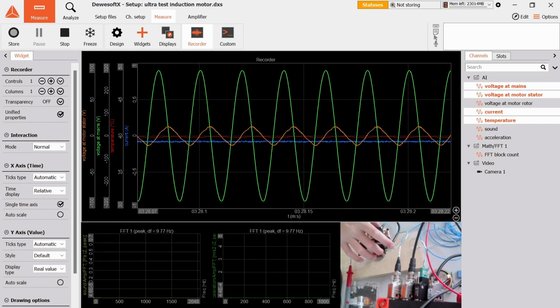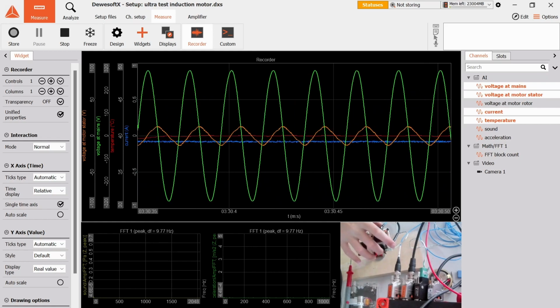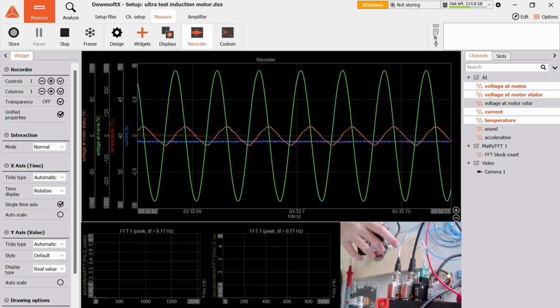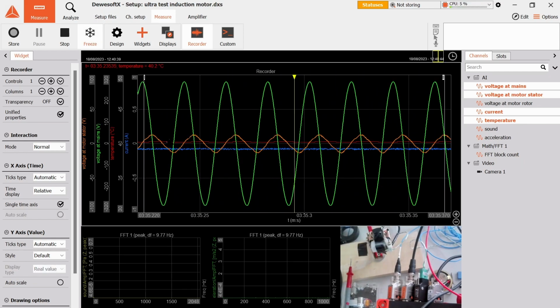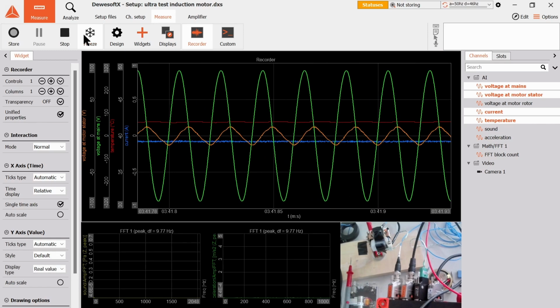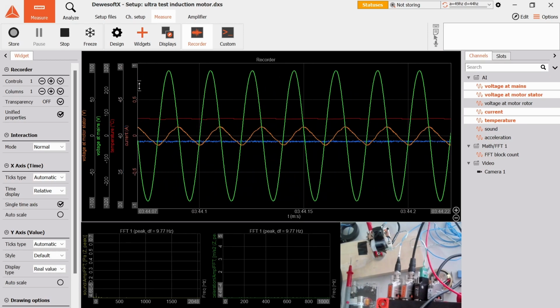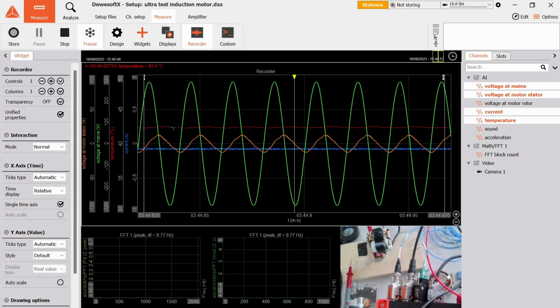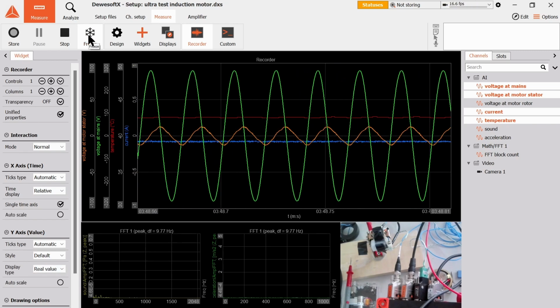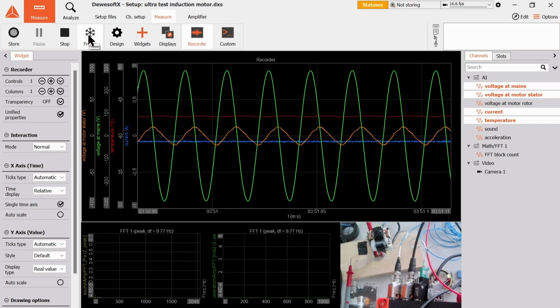If I push the thermocouple in, we can see the temperature rise to about 40 degrees Celsius, which is hotter than my finger. Oh, and it's now rising even more, you can see that it is 42, because now it's actually touching the rotor, so it's measuring temperature properly.